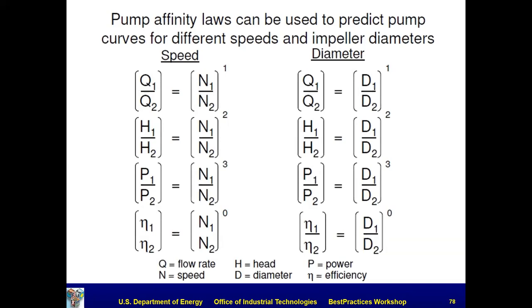I can have all kinds of different shapes of system curves. Okay, so all this does is modify the pump curve if I change speed, or if I operate at the same speed and I change diameter by trimming an impeller. So these are not appropriate for directly estimating operating points, only for adjusting pump curves.